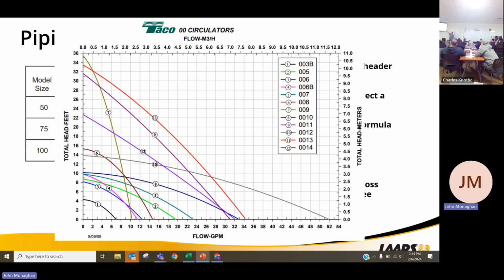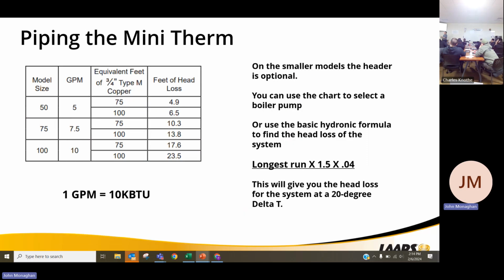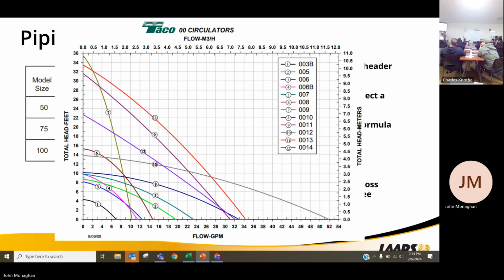The 007 is going to be number 5. It's going to be right here in this chart. Most of our homes, if we go back to that chart, we'll use the 75. We have 10.3 feet of head loss. I need to move 7.5 gallons a minute. Come back to that chart, 7.5 gallons a minute.